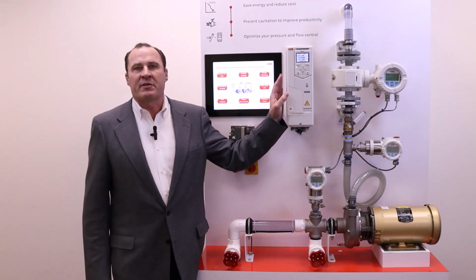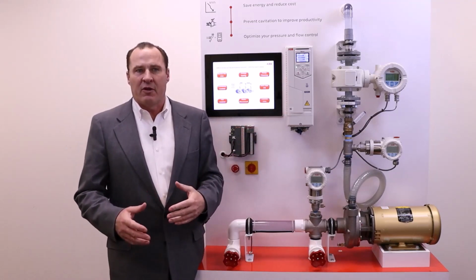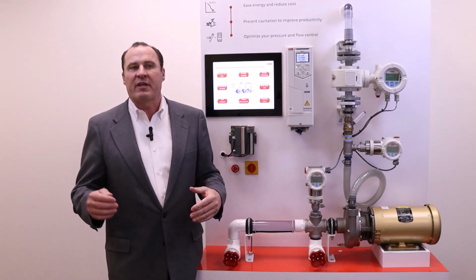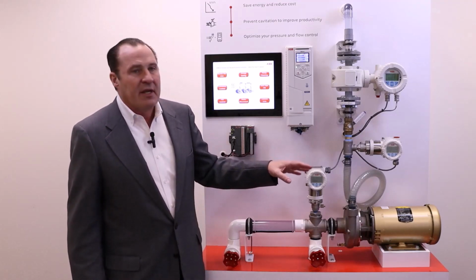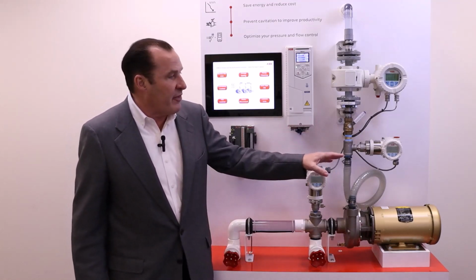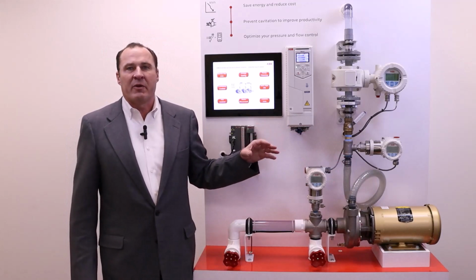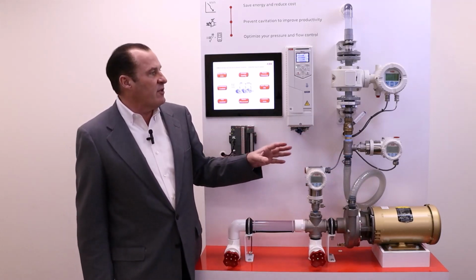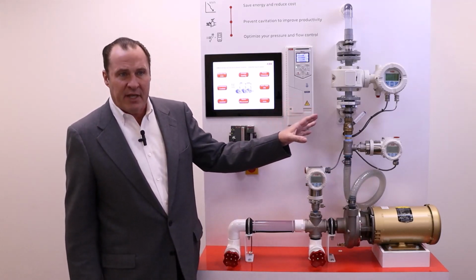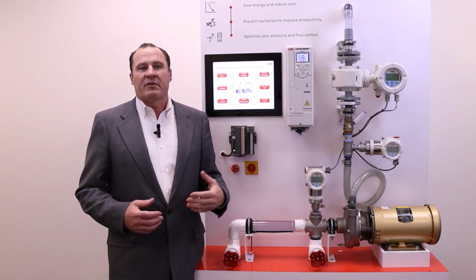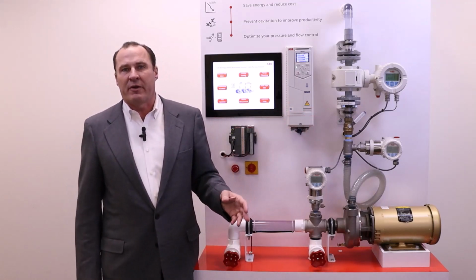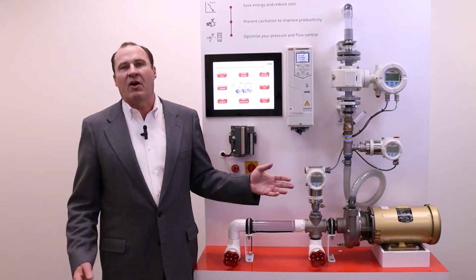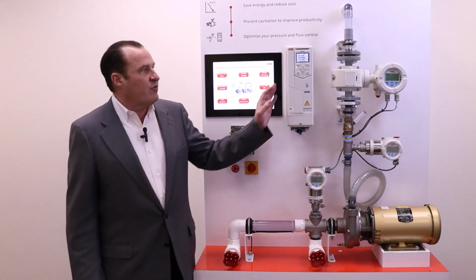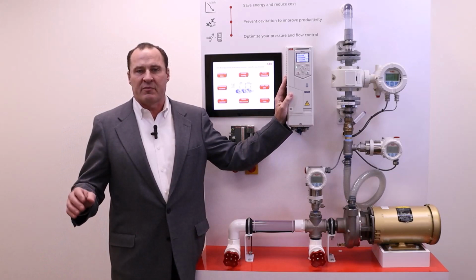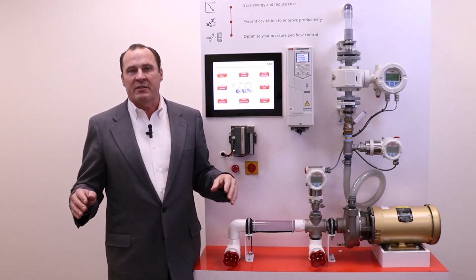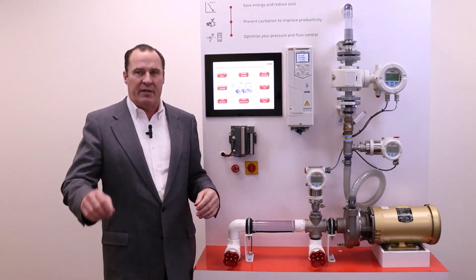The drive uses the relationship of power to flow and flow to head pressure to calculate the required pump speed needed for the head pressure at the pump, allowing the pumping requirements to be met without the use of an external feedback pressure sensor. With the elimination of external pressure sensors and associated wiring, overall installation time and costs are reduced. The drive is the controller of the system, reducing the need for expensive external hardware, saving you money.